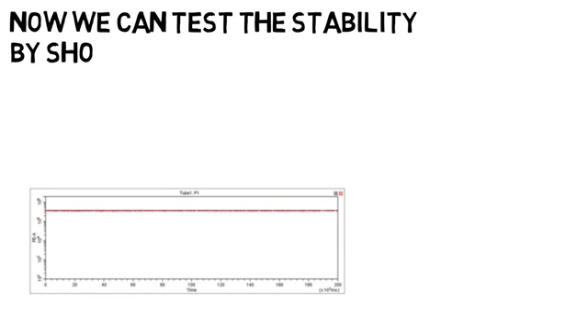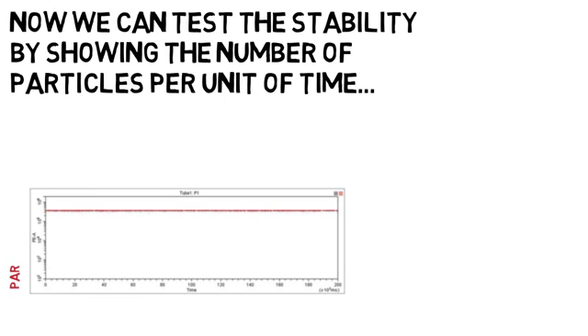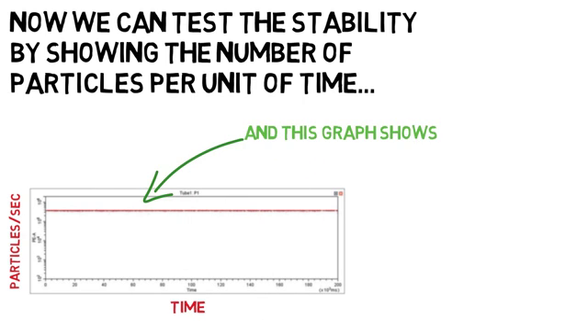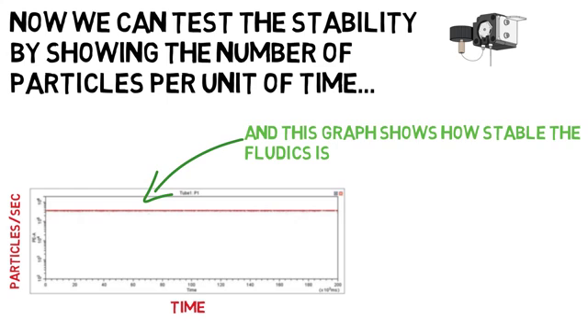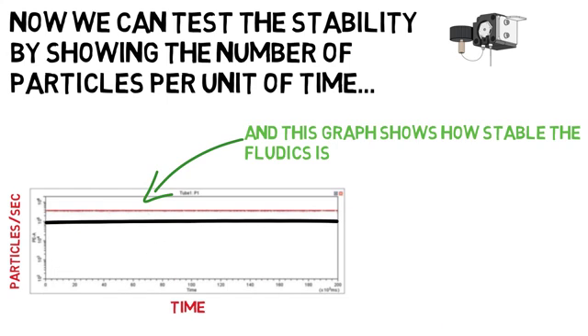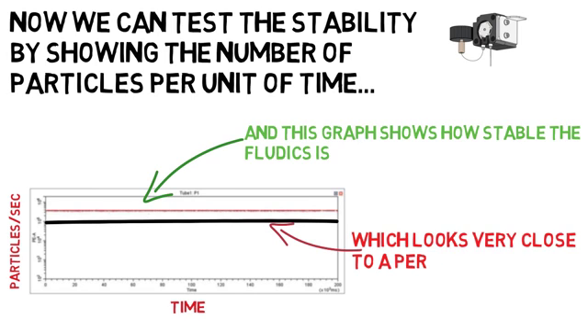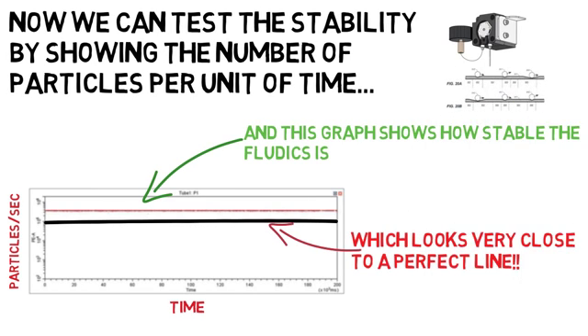What we see when we monitor sample number versus time is a perfectly flat line. This implies that the peristaltic pump is not creating pulses, which is really important. This is related to the unique design of the pump, so that any pulses are removed using a clever design feature of the pump itself.